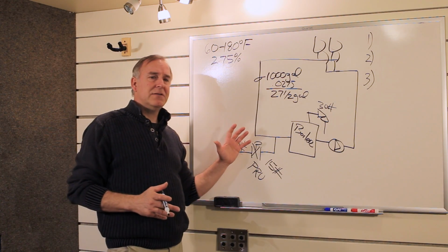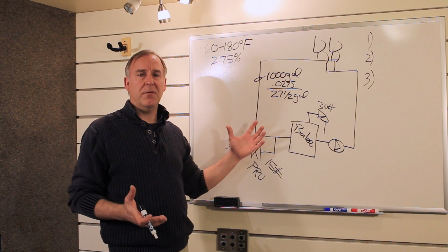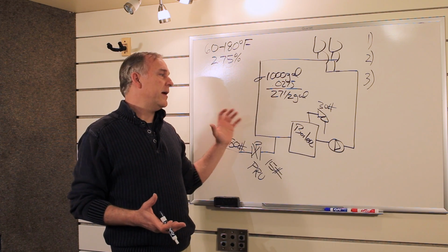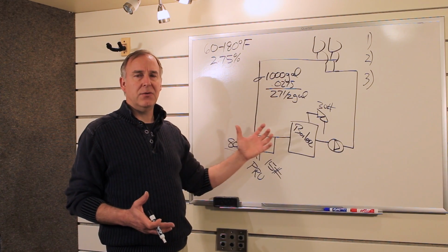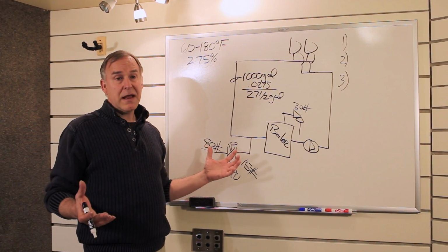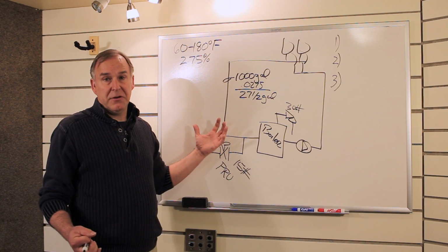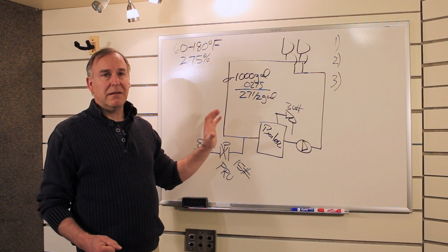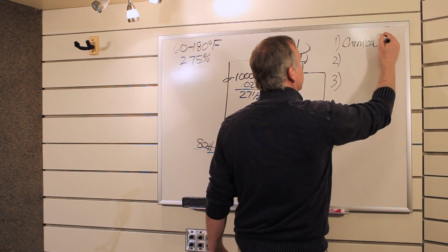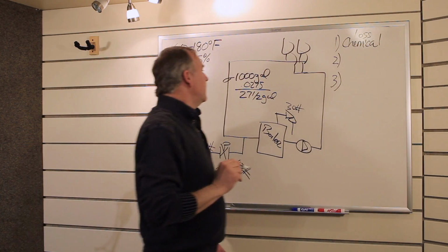If you think about systems and the chemical treatment that we put in them, sometimes we use a glycol mixture in there for freeze protection. My goodness, if we were dumping that down the drain every time we heated and cooled the system up, glycol, a 5-gallon pail of that stuff can be $100 easy. So that would be a lot of money down the drain. So loss of chemical treatment or glycol would be a compelling reason why this would not be a good scenario.